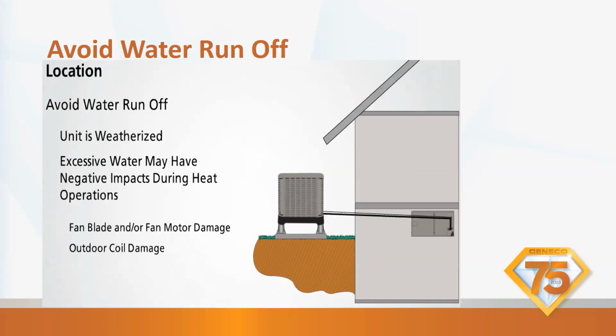Make sure that you're putting your unit outside of the drip line or all the way inside of the drip line. I know now they're making some houses that have 4-foot eaves. So you want to be careful that you maintain your 5 feet above the unit to the eave, and then don't let the water drip inside the unit. You'll get fan blade damage, motor damage, outdoor coil damage, because remember, the defrost only defrosts the coil. It does not defrost inside of the unit. So if you've got water dripping off the roof into the unit when the unit's off, it can freeze and build up like a cone right on the inside, and it can break pipes, it can crush coils, it can take out fan blades.